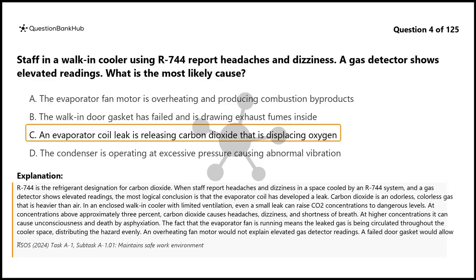The fact that the evaporator fan is running means the leaked gas is being circulated throughout the cooler space, distributing the hazard evenly. An overheating fan motor would not explain elevated gas detector readings. A failed door gasket would allow warm air in but not toxic gas. Excessive condenser pressure is unrelated to the symptoms described.